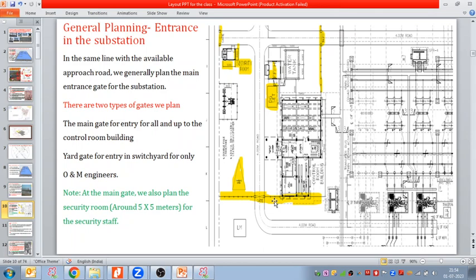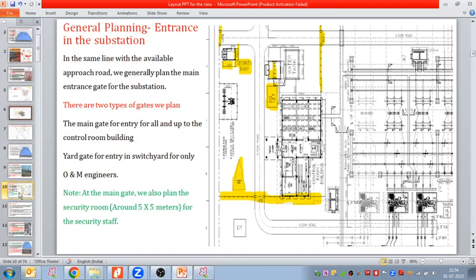Usually at each corner of the fencing, and after every 10 meters - or as utility practice, after 20 meters - we have to connect this fence with the common ground grid of the substation. We will discuss that later during the earthing module.